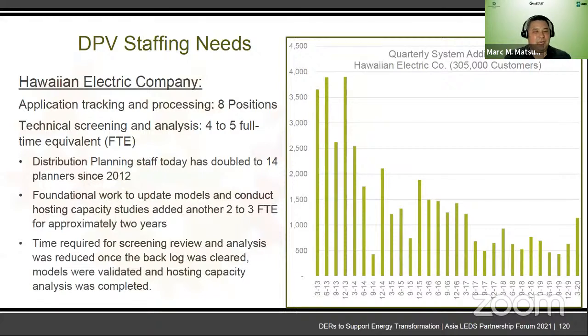It doesn't happen by itself, right? You need people. So for an organization with 300,000 customers, a fairly small utility, they have 8 positions for intake of applications, processing applications, and interacting with customers. They have 4 to 5 full-time equivalent effort doing the screening and the interconnection impact analysis. So in that time I talked about, 2008 to 2013, they had to really staff up. Their staffing doubled in that time to get that kind of stuff done. The foundational work to do the hosting capacity analysis on every distribution circuit and figure out the connection limit for each circuit took 2 to 3 people about 2 years to work through all those circuits.